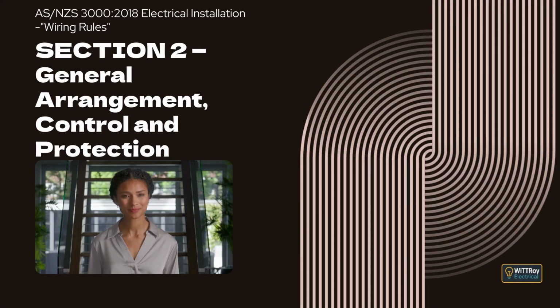Clause 2.5.4.4, alternative position of short-circuit protective device, explains that in some situations the protective device does not need to be located exactly at the circuit origin. One situation is where the conductor section between the origin and the device is very short, is mechanically protected to reduce the likelihood of a short circuit, and is installed in a way that minimizes fire risk.